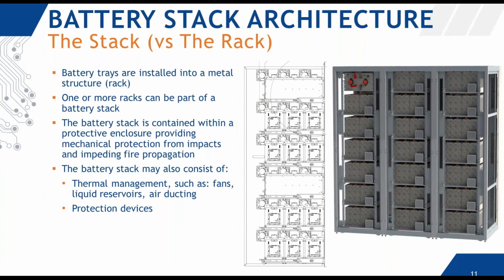And the battery stack is also contained within a protective enclosure to provide mechanical protection from impacts, but also to impede fire propagation. And I should pause a little bit on this third bullet, which was specific around fire propagation, because that is a test that's carried out as part of UL 1973. Most of us in the US are familiar with the International Fire Code and the NFPA regulations that, depending on the size of the battery stack, you may have to go through a UL 9540A large scale fire testing. But UL 1973 also carries out a test where they will observe fire propagation within a given battery stack, and they're checking to make sure that there's no flame propagation, so there's no flames coming out or an explosion. So the design of that enclosure actually is important when it comes to a 1973 system.